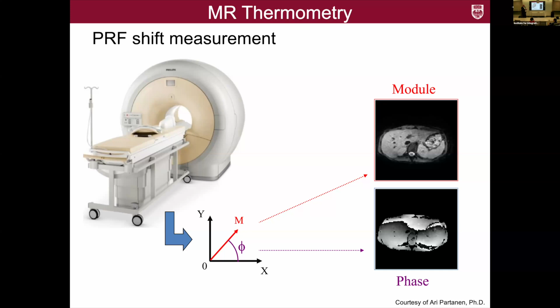And this phase shift we can determine by looking at these parameters that are also important in MRI. We have the gyromagnetic ratio of 42.5 megahertz per Tesla. Then we have the MRI parameters, the echo time, and the magnetic field, 1.5 T normally for the treatments. We use the 3T system because it gives a little bit higher signal to noise ratio, but it's often difficult with studies to use it, because if you do cardiac studies, there are a lot of motion artifacts and susceptibility artifacts that might be stronger. But we were pretty successful using our 3T system for HIFU treatment.